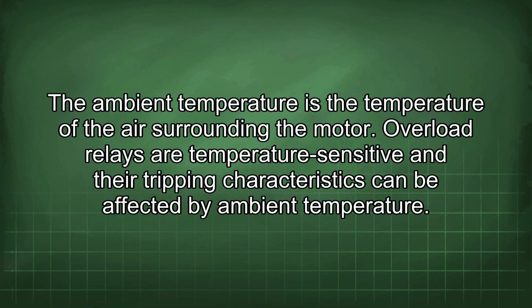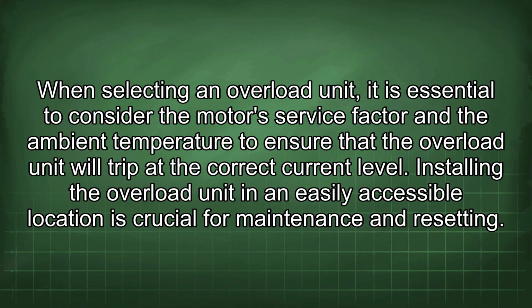The ambient temperature is the temperature of the air surrounding the motor. Overload relays are temperature sensitive, and their tripping characteristics can be affected by ambient temperature. When selecting an overload unit, it is essential to consider the motor's service factor and the ambient temperature to ensure that the overload unit will trip at the correct current level.